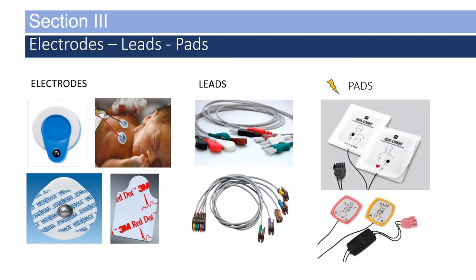Leads or wires should be checked for integrity — make sure there are no cuts or frays. Multi-purpose pads are also available in infant, child, and adult sizes. Electrical therapy may be applied including defibrillation, synchronized cardioversion, and transcutaneous pacing.